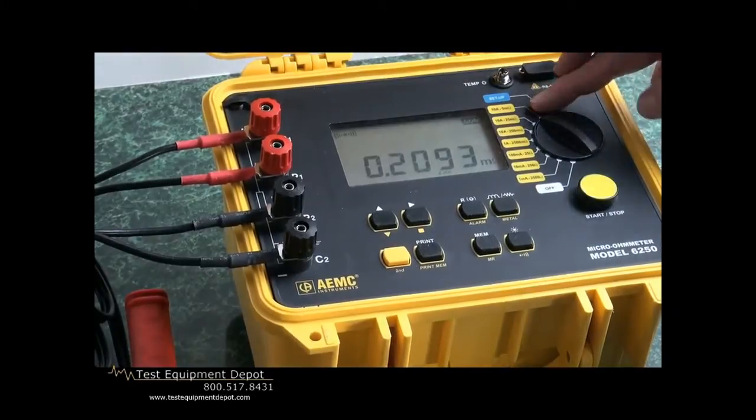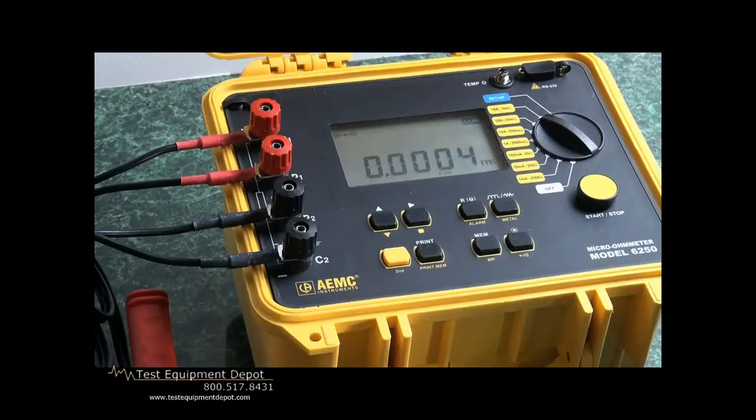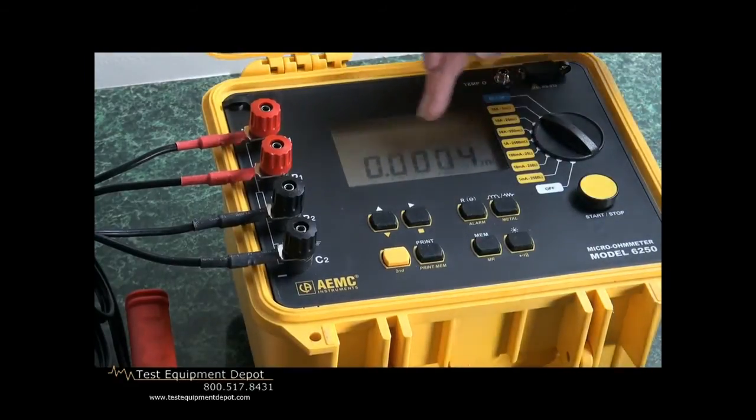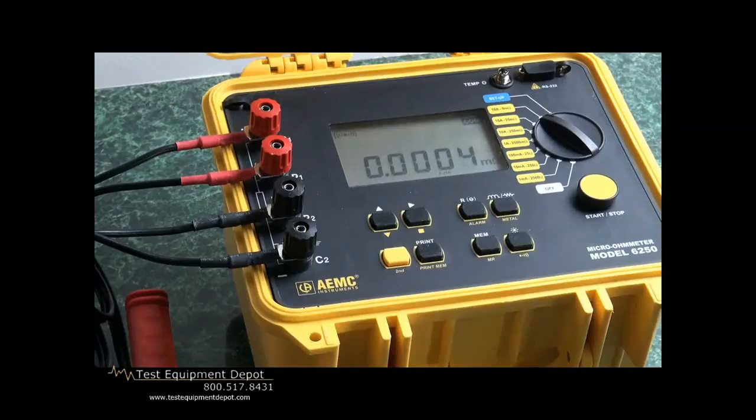Now we'll conduct a new test. We'll move it to the 10 amp position, and we will go ahead and test. This conductor is actually very good because it is 0.0004 micro-ohms. That just demonstrates the sensitivity of this meter.